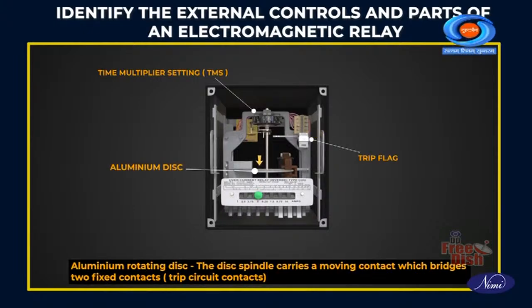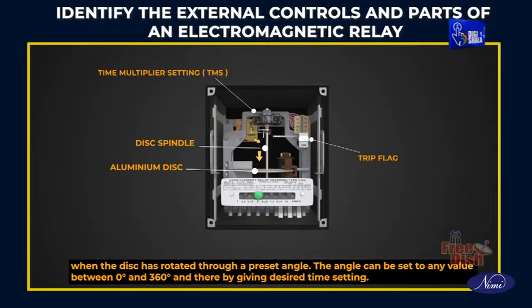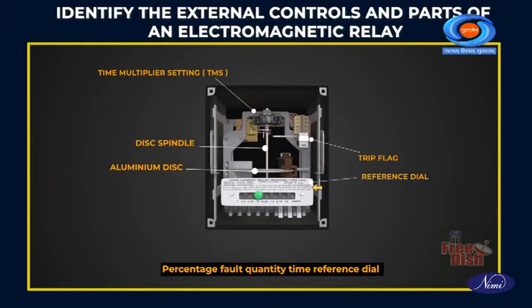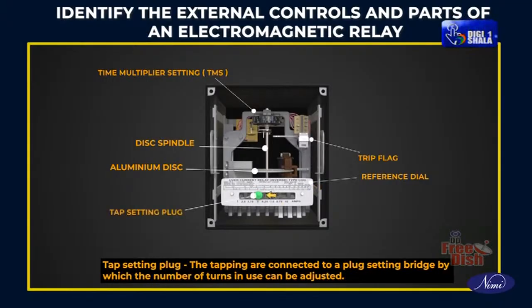Aluminium rotating disc. The disc spindle carries a moving contact which bridges two fixed contacts when the disc has rotated through a preset angle. The angle can be set to any value between 0 degrees and 360 degrees, thereby giving the desired time setting. Percentage fault quantity time reference dial. Tap setting plug.